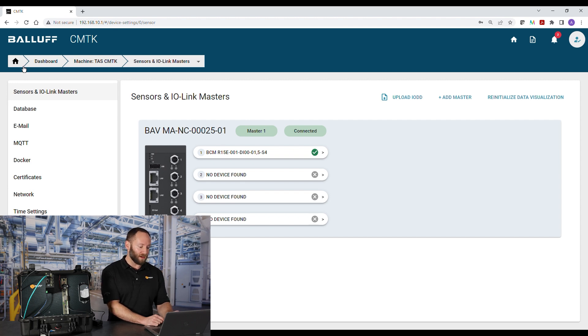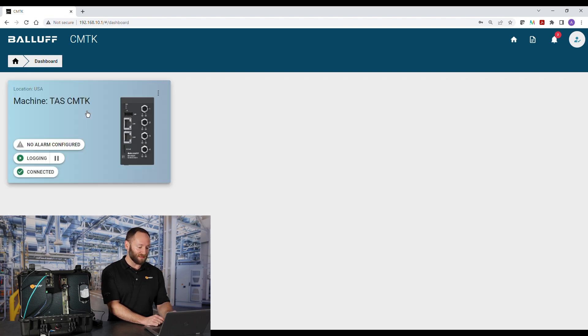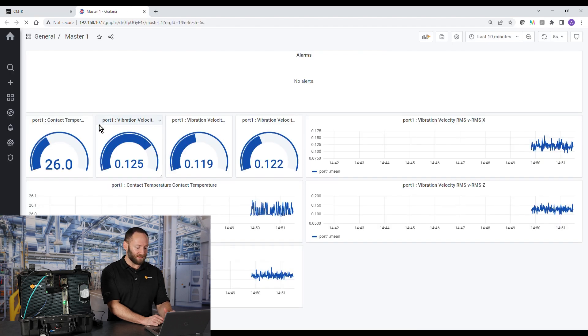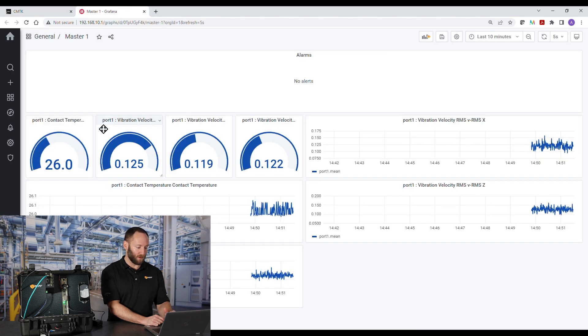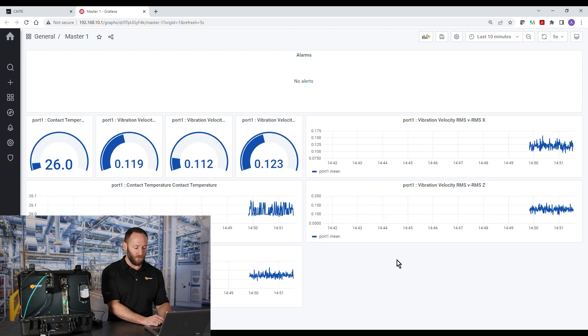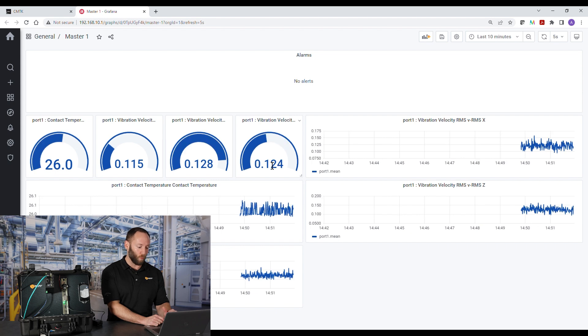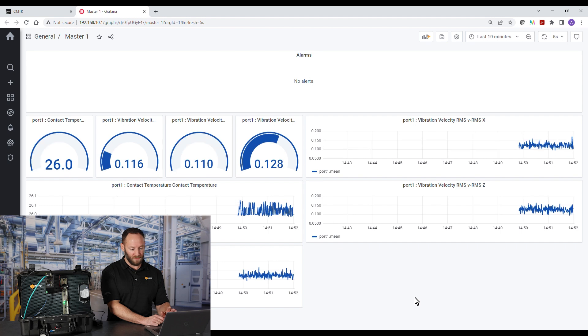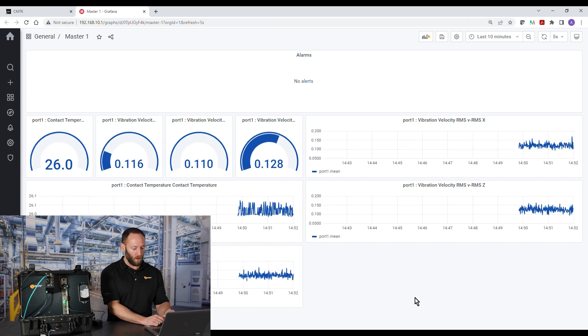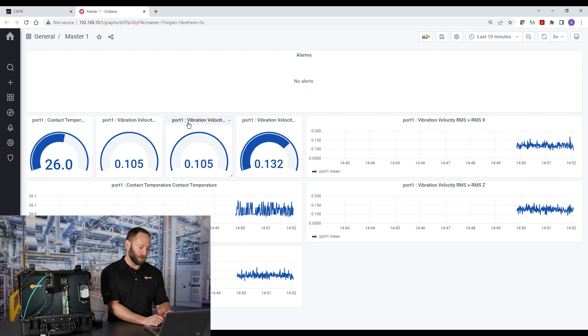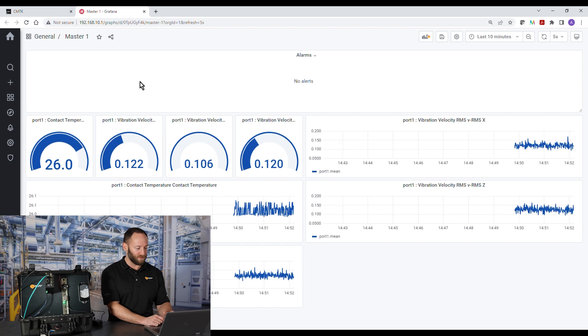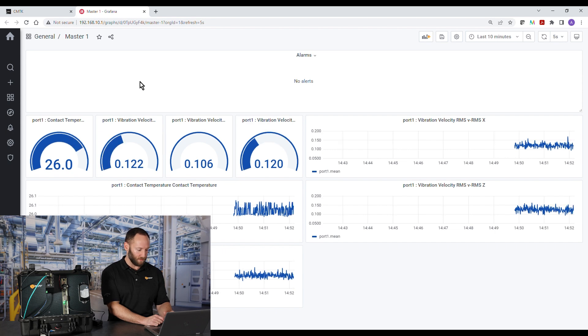Next, we'll go to the main dashboard and click the main tile. That's going to launch Grafana. And here we can see the default graphical interface. So by default, the software generates a graph and gauge for each variable on the sensor. So in the case of the BCM sensor, we have contact temperature and vibration velocity RMS on the X, Y, and Z axis. So you have four gauges, four graphs. All these graphs by default are blue and auto-scaled. And the information is default. So in this video, we're going to talk about how to change the color to basically represent the ISO standard.